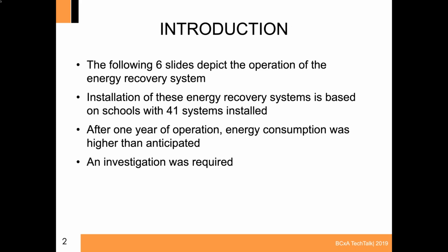So the following 6 slides are going to depict the basic operation of an energy recovery system using energy recovery cores. These were based on 41 systems that were installed in schools across Saskatchewan. After the initial year of operation, the energy consumption was about 20% higher than what was anticipated. In some schools, it was more. And because of this, an investigation was required about 18 months after substantial completion as to why this was happening.